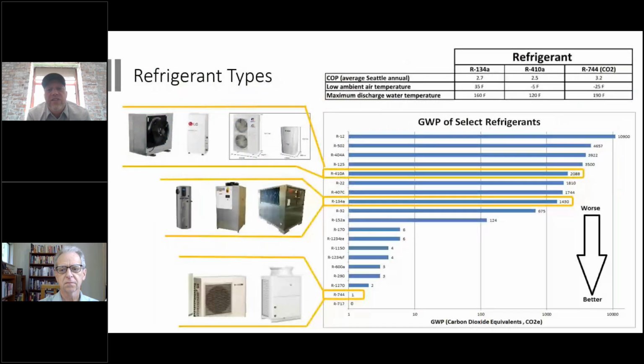to kind of talk. Yeah, so this one talks about the refrigerants, but there's essentially for water heating sort of 3 refrigerants, or actually 4. So there's 134A, that's pretty common. That cycle doesn't do well with really cold temps. So that's a great candidate for either indoor or in a buffered parking garage.